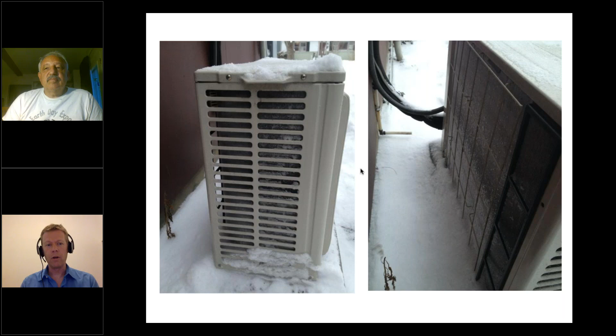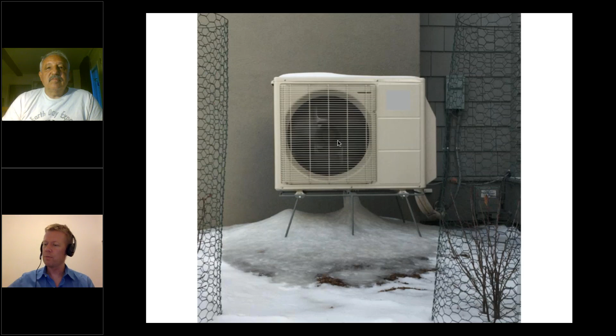And that can be a real problem. So in cold climates with a lot of snow load, you really need to raise these off the ground. Something like this kind of stand that gets them off the ground about a foot. This is that Minneapolis location. The owner has actually gone back and raised this heat pump up even further. And the reason for that is that during defrost mode, they were getting refreeze off of their defrost melt. So you can see the defrost melt here, refreezing on the ground and then starting to creep back up. This particular model does not have a drain pan heater. Some models do. So that's going to be something that you should look at when you are selecting equipment, whether or not a drain pan heater is needed, whether it's an optional extra for your particular system. And what kind of safety attributes you're looking at, because you don't want your defrost to start creeping up the backside of that heat exchanger.